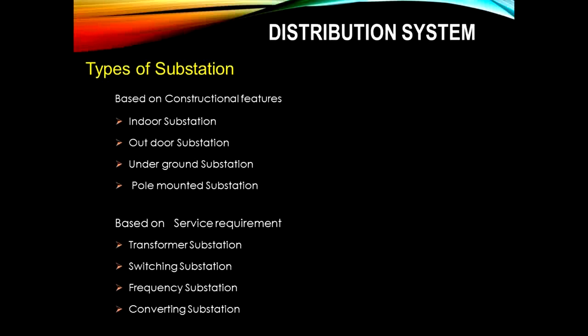Converting substations are used for HVDC stations, converting AC to DC and DC to AC. In India we use AC power, but DC transmission is useful for high level voltage transmission above about 500 kilometers, where HVDC becomes economically advantageous compared to AC systems. Since we use AC power, AC has to be converted to DC and DC back to AC.